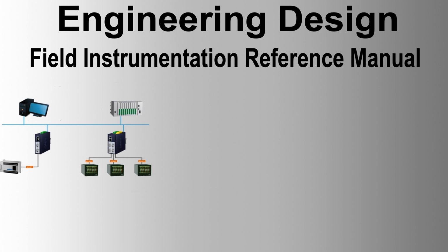Integral and receiving indicators. Integral or receiving indicators should be considered as an alternative to pressure and temperature gauges. Where a local indicator is required to support operating personnel, the physical location of the indicator should be selected so that it can be read from the intended operator position. If this requirement cannot be met by an integral indicator, a receiving indicator shall be applied.